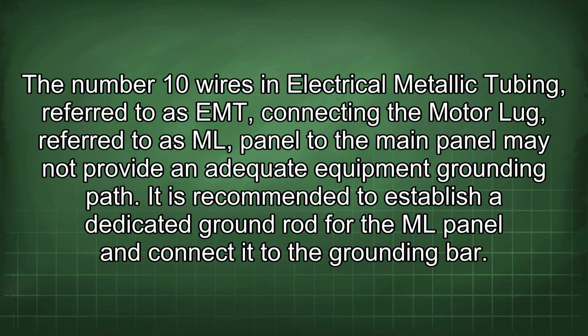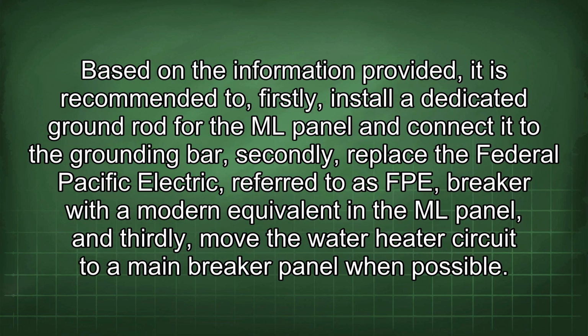It is recommended to establish a dedicated ground rod for the ML panel and connect it to the grounding bar. Based on the information provided, it is recommended to firstly install a dedicated ground rod for the ML panel and connect it to the grounding bar. Secondly, replace the Federal Pacific Electric, referred to as FPE, breaker with a modern equivalent in the ML panel. And thirdly, move the water heater circuit to a main breaker panel when possible.